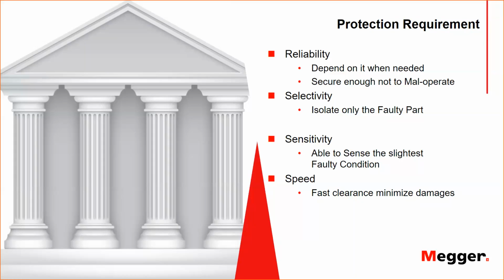Another criteria that I have is selectivity. Selectivity is the criteria that you can't always have, and sometimes you have to compromise on another criteria to get it. It is to isolate only and only the faulty part as much as possible. I don't want to turn off all my power system parts. I only want to turn off or isolate the faulty ones. And this selectivity, that's why we have a lot of settings related to timing, related to pickup currents or zones or something like that, just to achieve this selectivity.